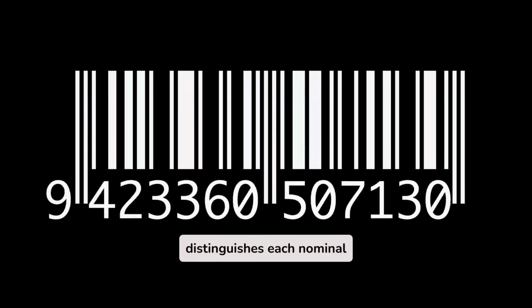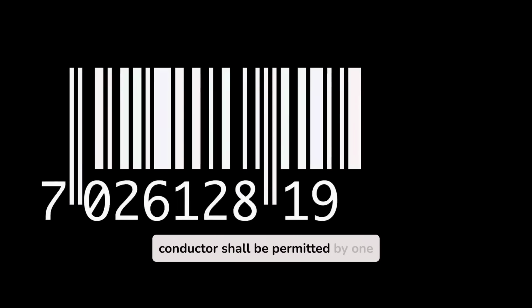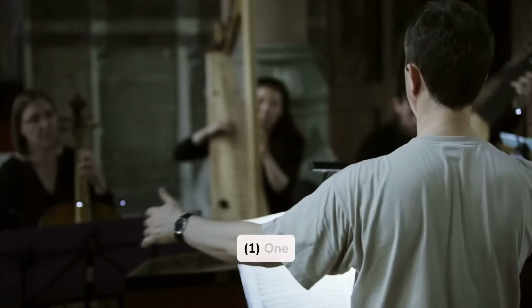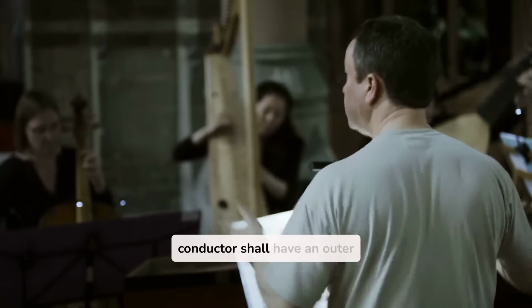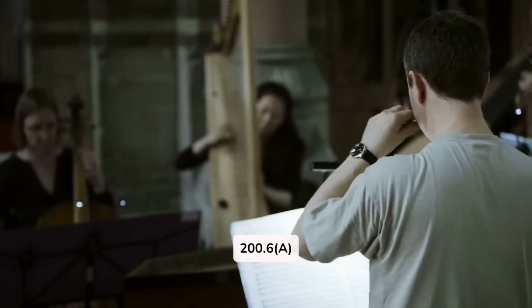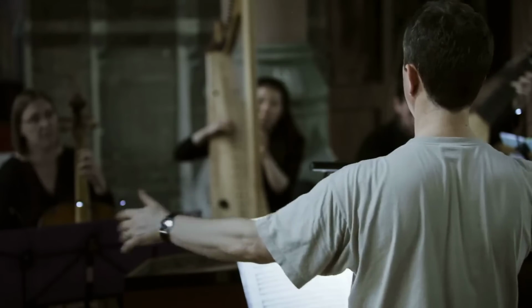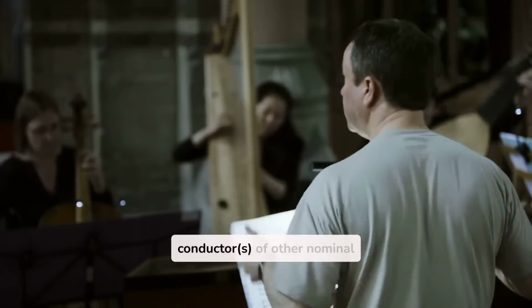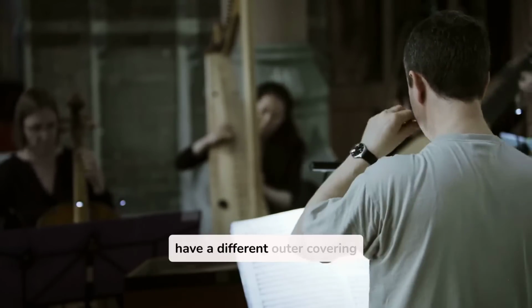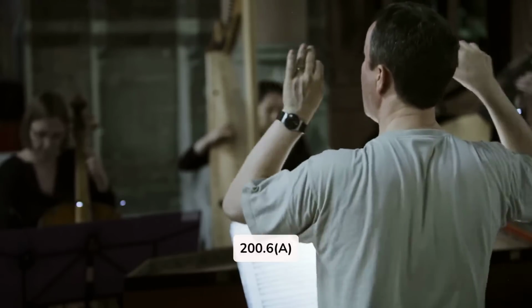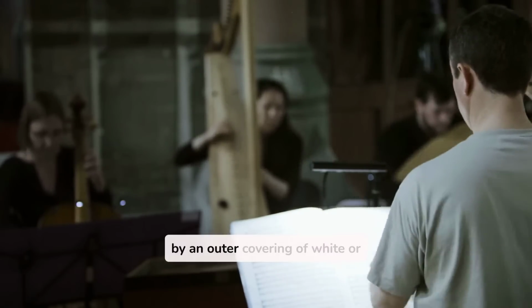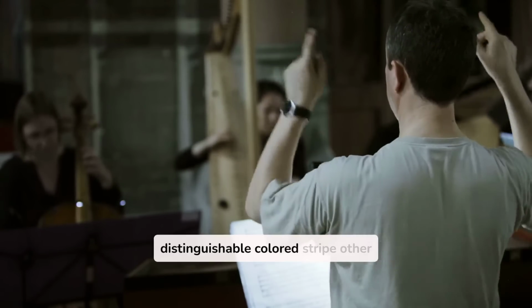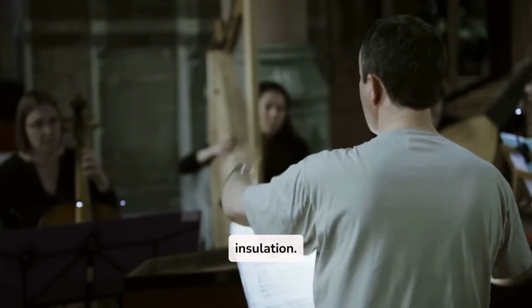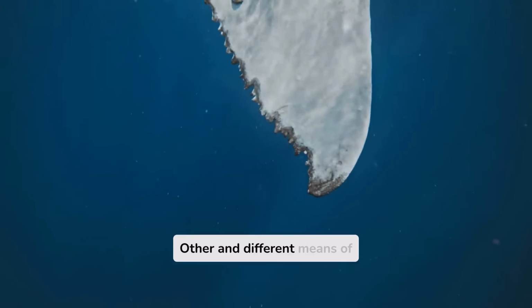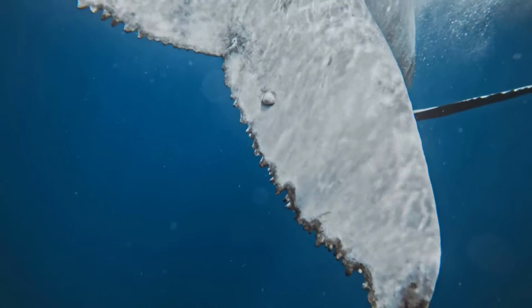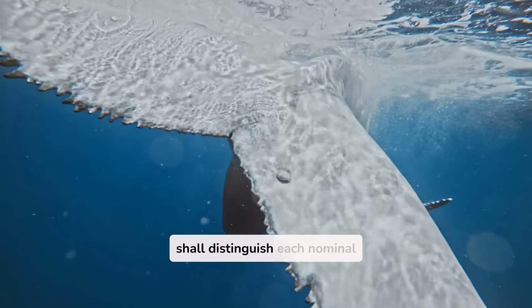Identification that distinguishes each nominal voltage system grounded conductor shall be permitted by one of the following means. 1. One nominal voltage system grounded conductor shall have an outer covering conforming to 200.6(A) or (B). 2. The grounded conductor of other nominal voltage systems shall have a different outer covering conforming to 200.6(A) or (B), or by an outer covering of white or gray with a distinguishable colored stripe other than green running along the insulation.